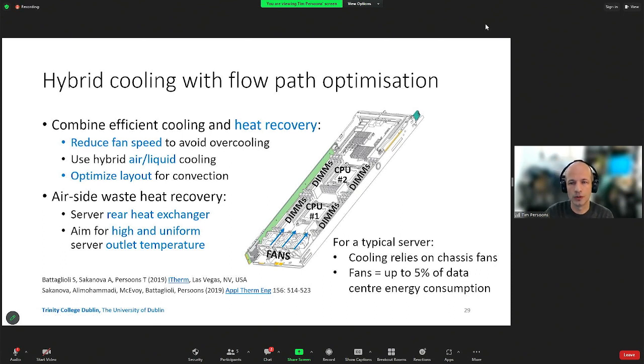And so the goal here is to increase the outlet temperature of the air at the outlet of the server over here. And the assumption then is that downstream of this, we have a heat exchanger where we can extract the heat from the air and bring it into a liquid stream. And the goal here is to aim for both a high temperature at the outlet, but also a uniform temperature at the outlet to maximize the performance of the heat exchanger.